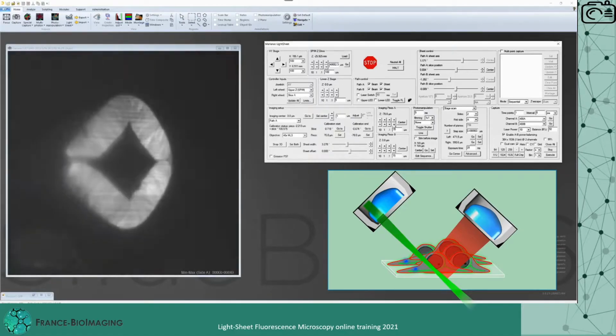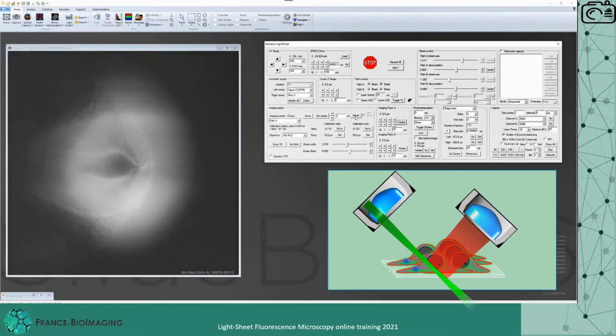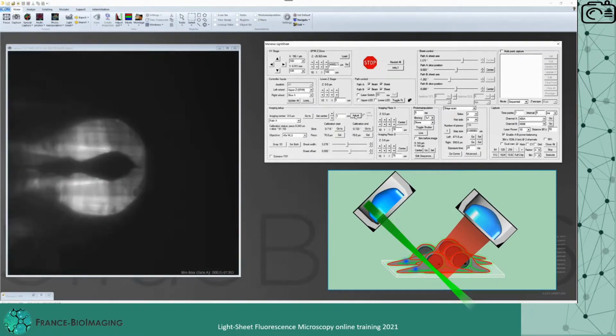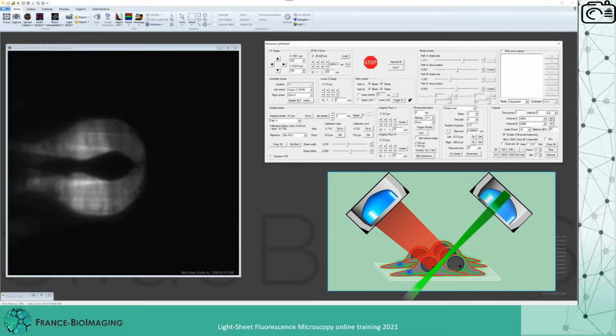We can check that all is in order by setting the objective to a central position and clicking Adjust. And the system will compute the correct light sheet corresponding position. We can see that the image is in focus, hence the calibration is correct for this path, and we can move on to path B. Our slicing range has been calibrated for 140 micron movement on the piezo.